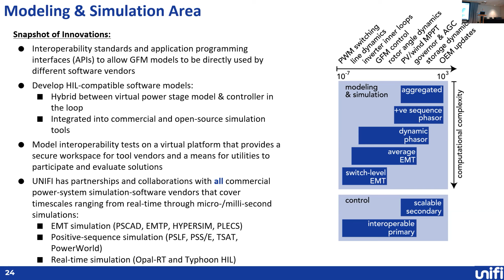In the controls area, when we talk about grid forming technologies, there's right now a lot of pathways for developing grid forming controls inside inverters. There's probably 4 or 5 different known ways of doing this. So what we're trying to do is come up with generic primary controls that would be embedded inside your inverters that people can use as a platform.